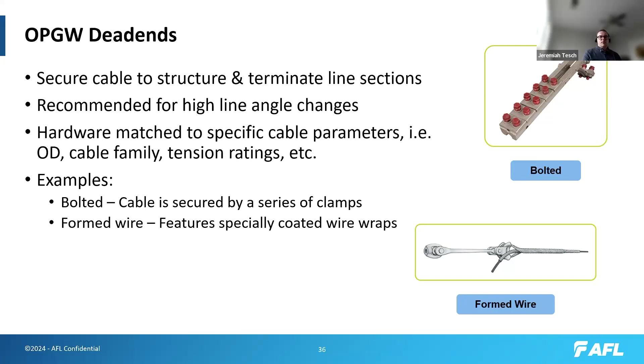So for optical ground wire, there are multiple styles. AFL offers a unique bolted style. The formed wire, though, is pretty common throughout the industry. So you have essentially flexible wire wraps that have a friction increasing coating that helps grip the cable a little bit more. And so this essentially just wraps the cable with wires that hold on to it. So there are different styles, but these are just a couple of examples for optical ground wire.